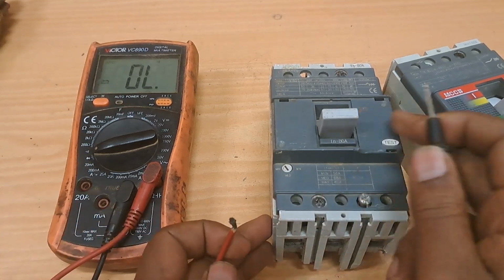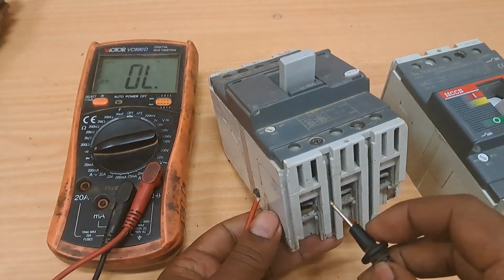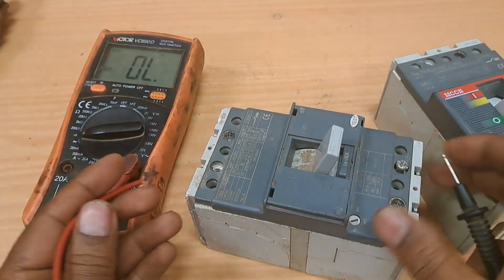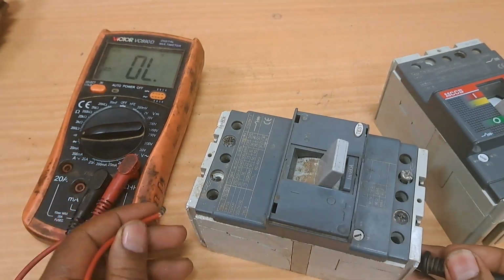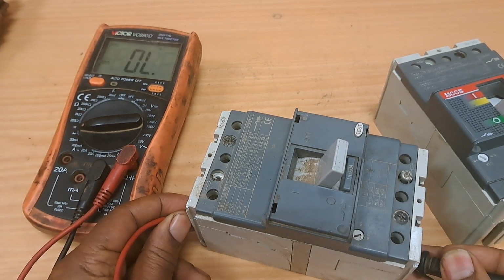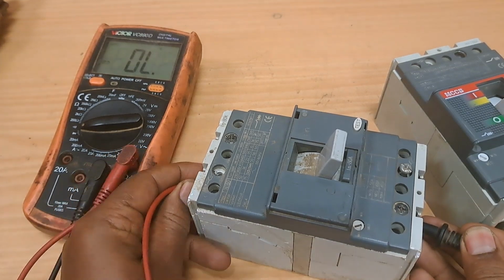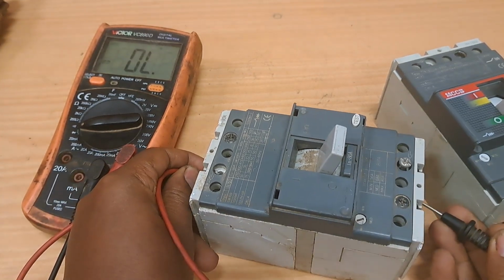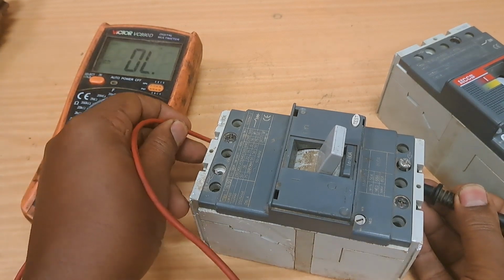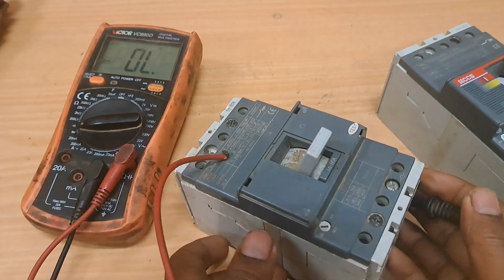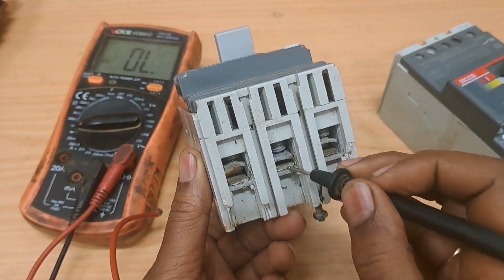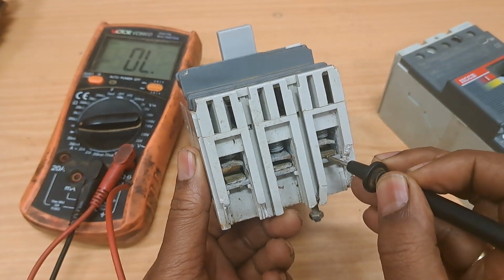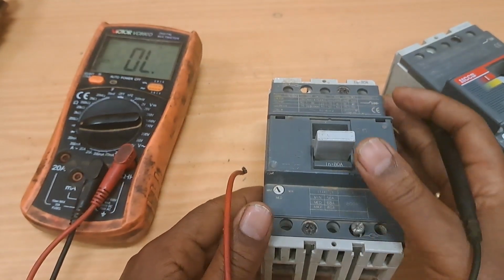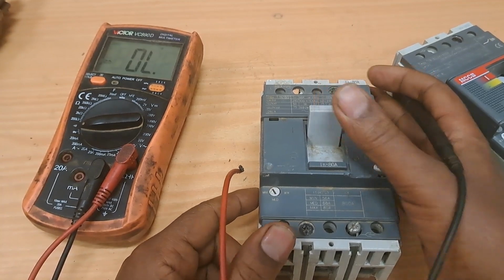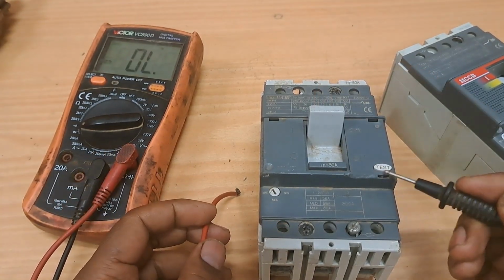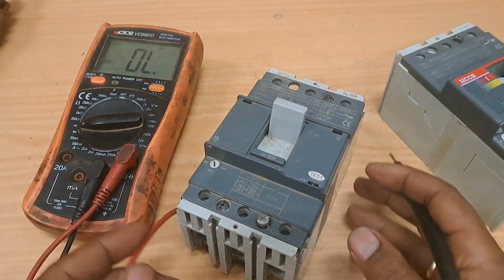Now look, when turned off, there should be no continuity between these terminals. Let's go ahead and confirm that. First terminal, there is no continuity. Second terminal, no continuity. Third terminal, no continuity. All you have to do is simply place your multimeter lead on here, and there should be no continuity when it is turned off. Let's go ahead and place it in the on position. Now there should be continuity across all the terminals. Let's go ahead and check.